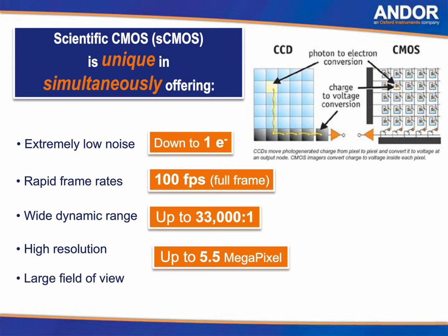If we move to the CMOS structure, it enters into effectively the pixel, but then can be read out through a buried channel immediately. So you no longer have to clock the charge all the way through the surface of the sensor, but you're able to bring it in and move it. So that is a CMOS structure. So what is a scientific CMOS? All scientific CMOS brings is the effective linearity of response for the CCD-like qualities to a CMOS structure. So what we've developed is effectively a CCD performance in a CMOS structure. So that gives us all of the advantage of fast clocking and the large field of view, which we then want to maximize.